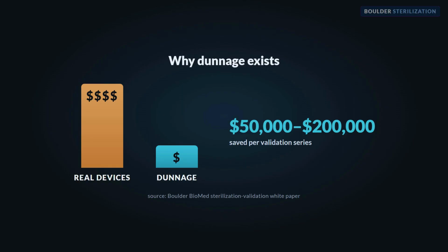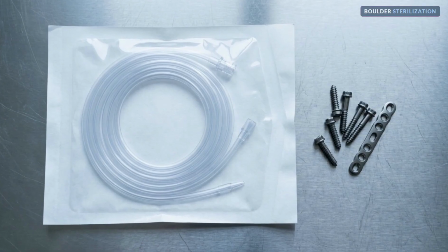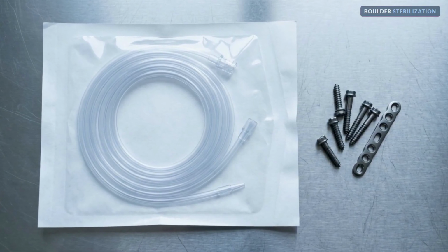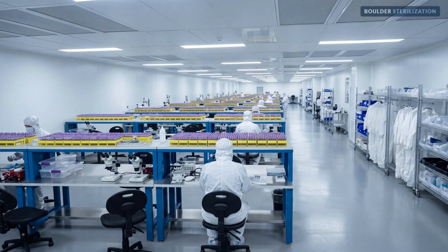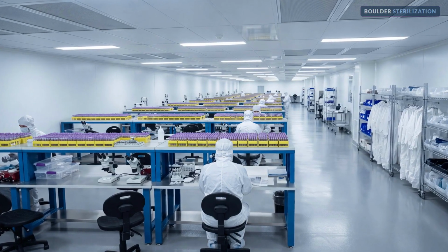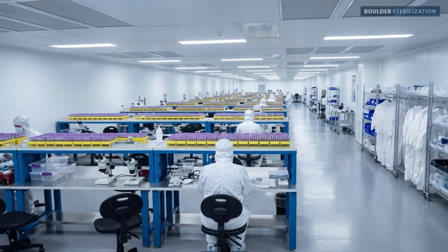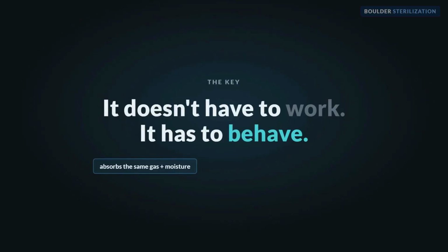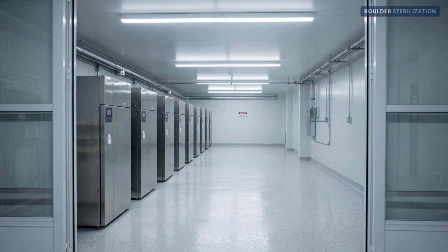So we fill it with a stand-in load that behaves like your product where it counts. That stand-in is Dunnage. The industry calls it a dummy load or simulated product. Using it instead of live devices can save you upwards of $50,000 to $200,000 in raw material and cleanroom assembly costs for a single validation series. So here's the key. Dunnage doesn't have to function as a device. It just has to behave like one where it counts. It has to face the same gas, absorb the same sterilant and moisture, hold the same heat, and block the same airflow. Do that, and the sterilization data carries over to your real product.